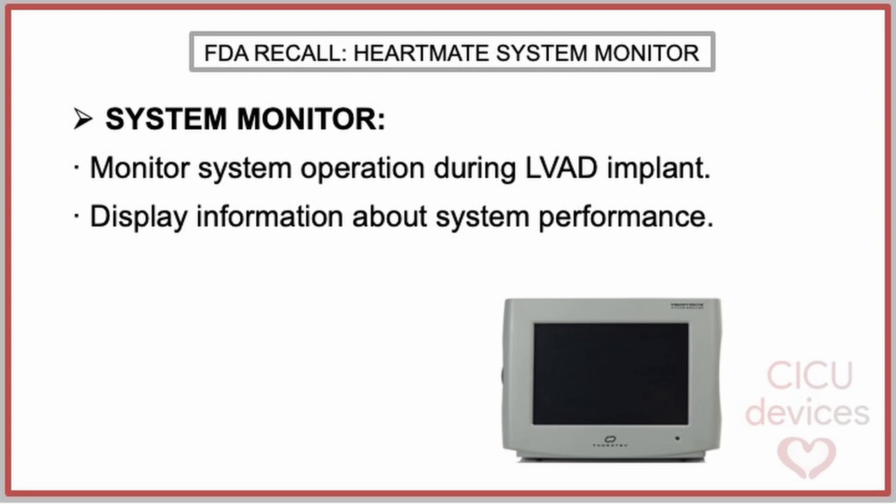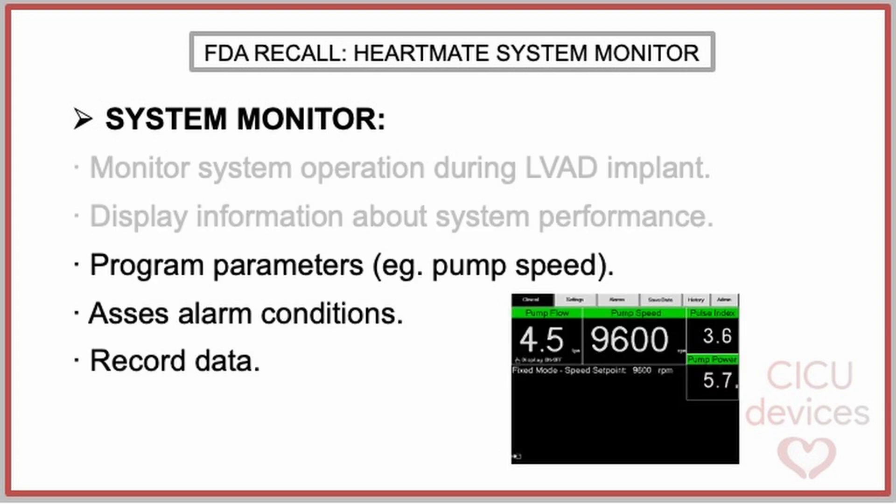The system monitor displays information about system performance, including current operating mode, pump flow, pump speed, and overall operational status. It is also used to program system parameters such as pump speed, assess and track alarm conditions, view and save performance data, and record data at specific intervals for review and analysis.